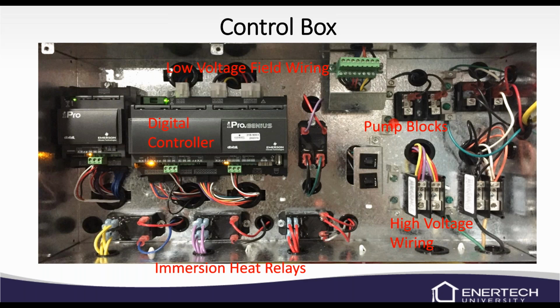We've got pump blocks. If you have a fixed speed pump because you need more pumping, we do have a pump block for that. And we also have a pump block for the variable speed pump. They're labeled in the unit, not like this, but they'll have stickers that'll let you know which one is your fixed speed pump block and which is your variable speed pump block. We've got a pump block for your electric immersion heaters and for the compressor as well. So this one here is for your electric immersion heaters, and this is for the compressor itself.